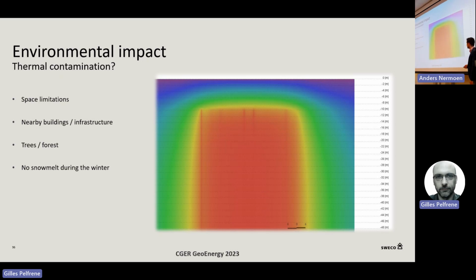The last slide covers thermal contamination - how can we prevent this to some extent, and how can we protect the trees? We're looking at insulating the first 10 meters of the casing. So we drill, install the bore heat exchangers, and then apply insulation at the top to prevent thermal interaction with the clay, especially since there are trees with roots nearby. On top of this we still have about 60 centimeters of another insulation layer, which prevents snow melt and thermal energy losses up to the surface.